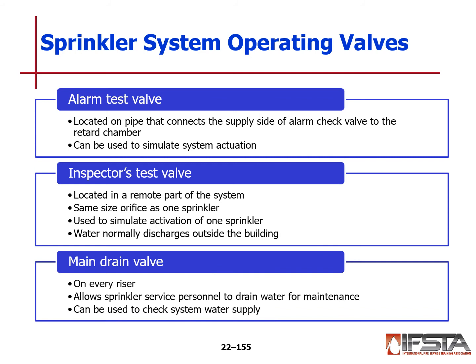The inspector's test valve is located in a remote part of the system, with the same size orifice as a sprinkler, basically. This is used to simulate activation of one sprinkler head, and the water normally discharges out to the outside of the building. And then the main drain valve. On every riser, you'll have a main drain valve. This allows the sprinkler service personnel to drain the water down for maintenance. This can be used to check the system's water supply as well.